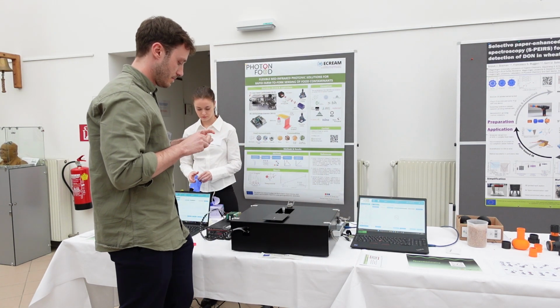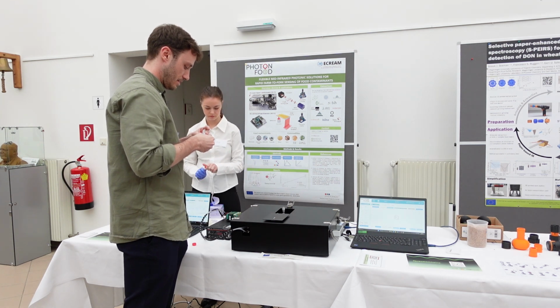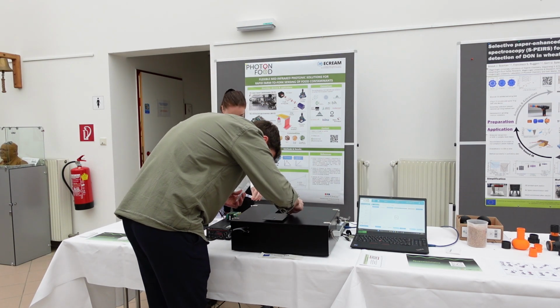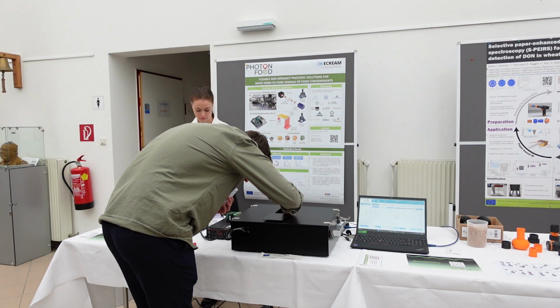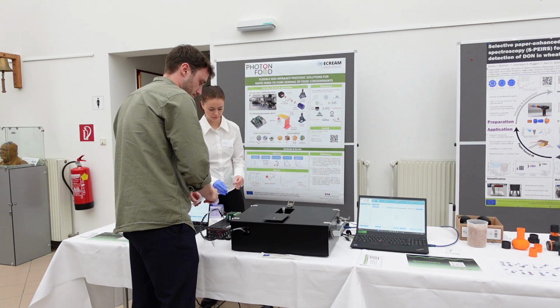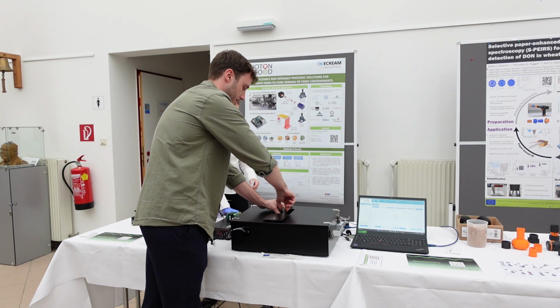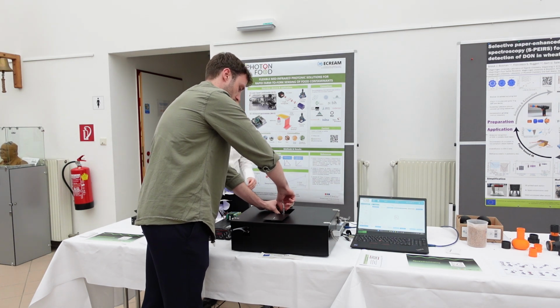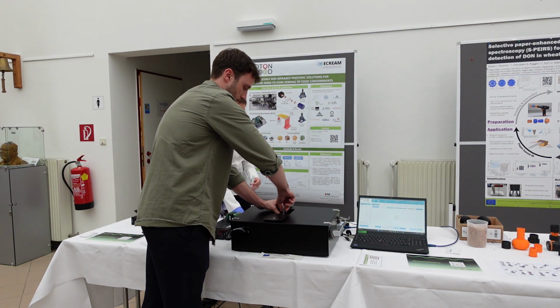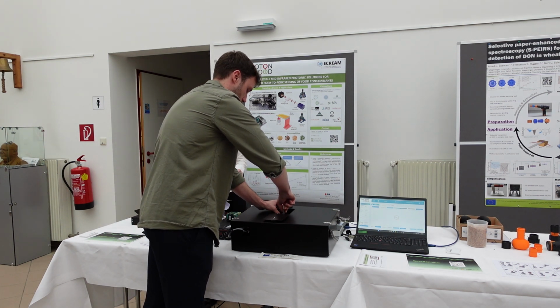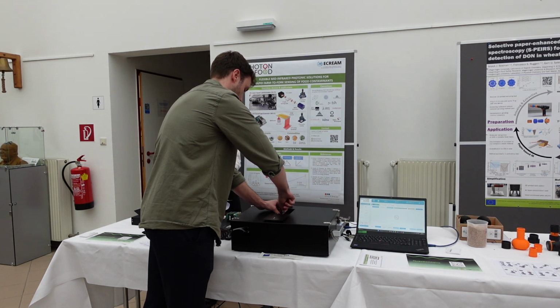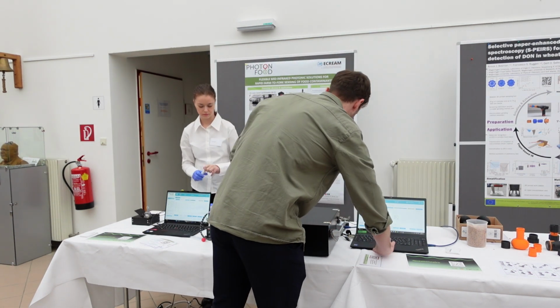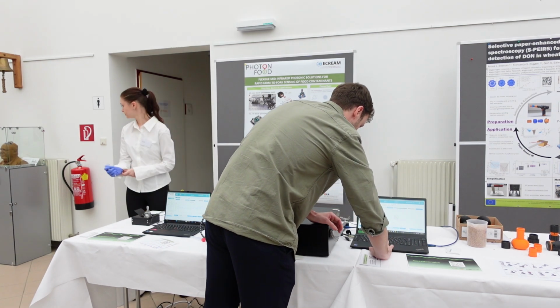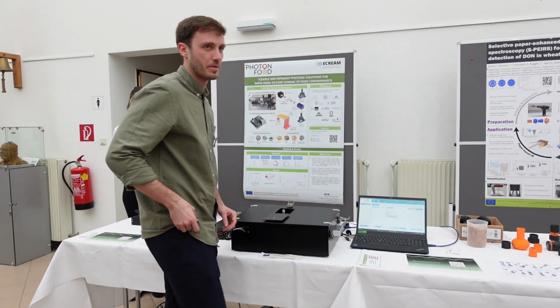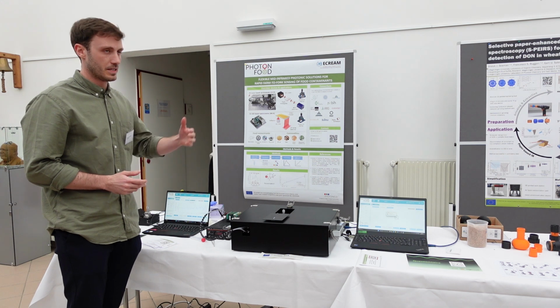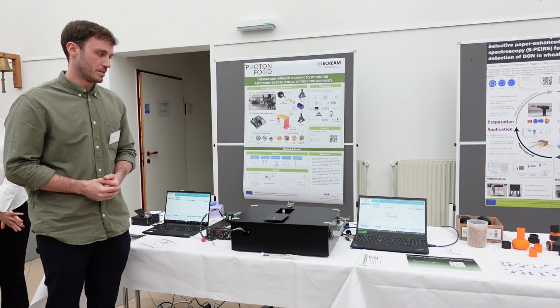and we would place the sample on top of the waveguide, the same as with the MiFi device. We would also screw the pressure stamp until the optimal pressure is reached. Once the sample is located, we just introduce the sample name and capture the spectra. It will repeat the same steps, this time with the sample, and it will automatically calculate your absorbance spectra that you will see on the screen.